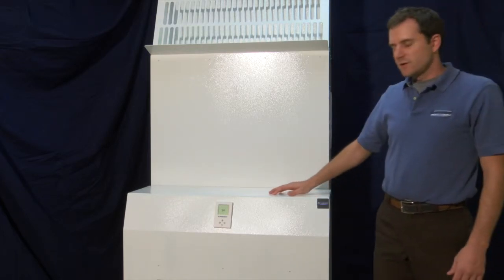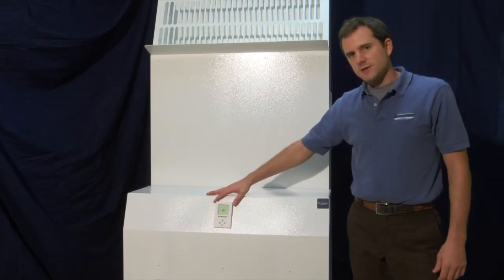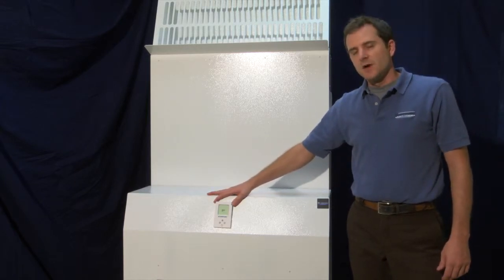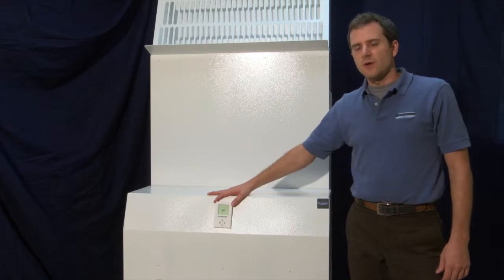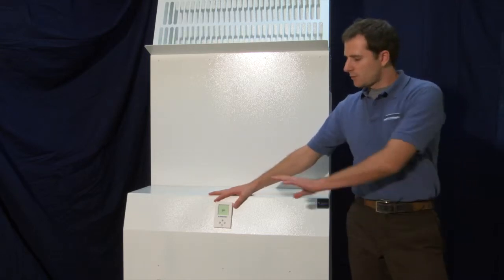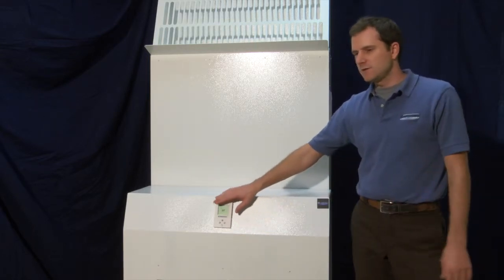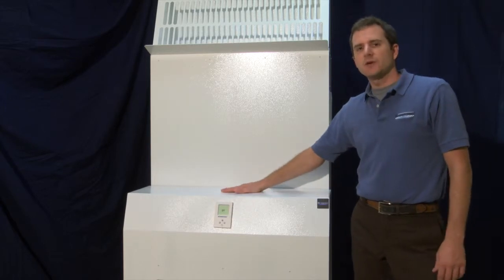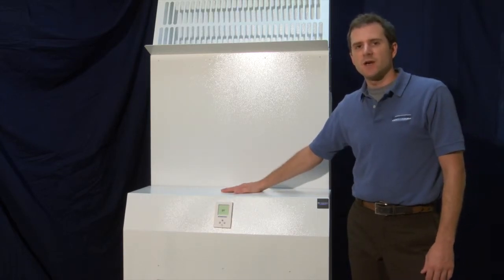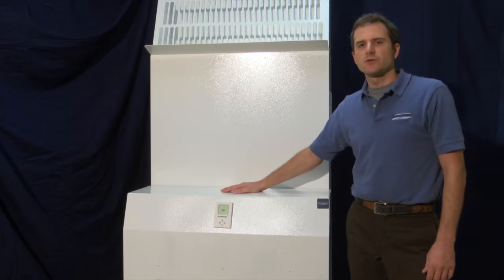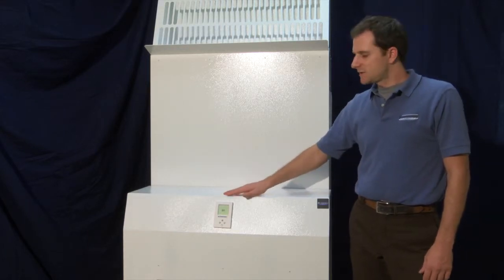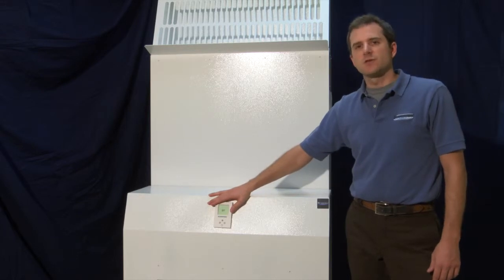The standard mist-free unit comes with a front-mounted digital humidistat. Note there are also other control options such as a remote humidistat wired back to the unit, dry contact points you can activate and deactivate yourself, and BMS and proportional control through our HC301 microprocessor. Let's take a closer look at the standard digital humidistat now.